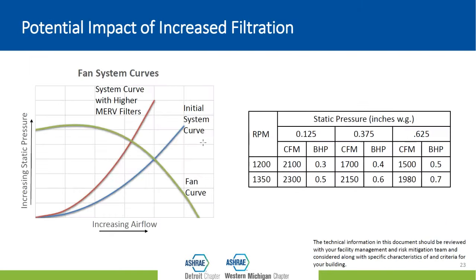Next slide. So when you increase your filtration levels, again, it impacts the fan's ability to move air throughout your system. This graphic here on the left shows the relationship between static pressure of your system and the airflow, the amount of air that you can move through that system. And if we look at the fan curve, we can see that as we increase static pressure, our airflow decreases, right? It gets less. And so if we start off with a system that has some MERV 8 filters in it, for example, it's going to have this blue system curve. And that intersection of that system curve and your fan curve is where your fan operates. And that's how much air you're moving through your system.